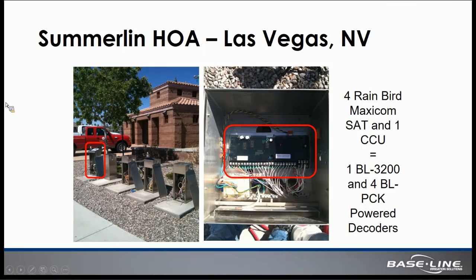Okay, so there was no new wire that was required for this retrofit. All of the wires that are shown here attached to this powered decoder are the existing or pre-existing valve control wires. They were run into the pedestals through the sweeps coming up into the PED. This powered decoder was just laid into that existing pedestal, powered off of the transformer that was pre-existing in the bottom of the pedestal, and no additional or new wire was required to be installed either in the landscape or at the controller locations.